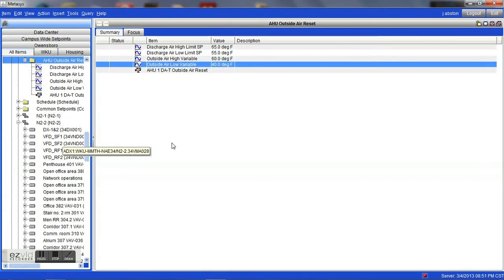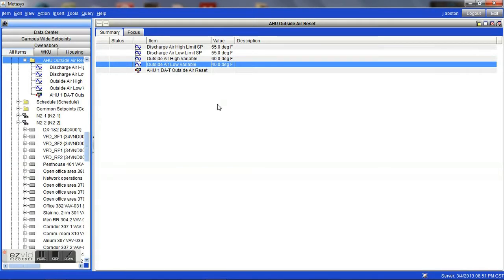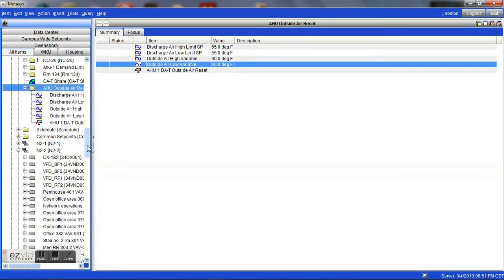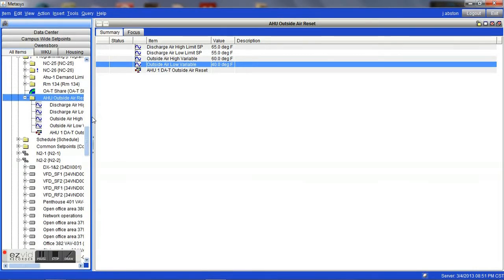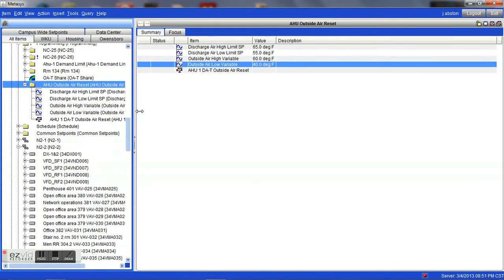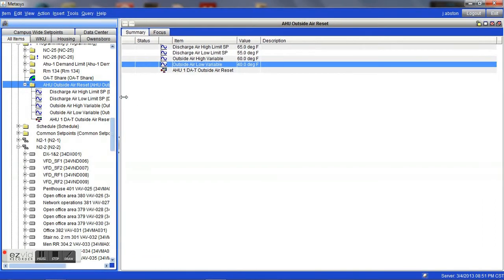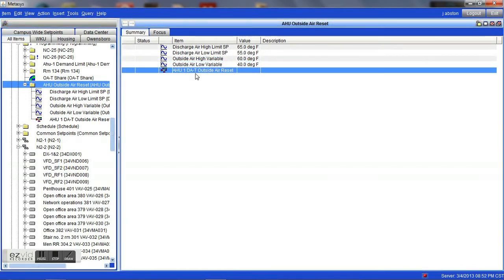One of the first things that we will need to do is to create a few analog value bits. This can be easily done through simply adding them to a folder somewhere where we can find them. Here you can see that I have them in a folder labeled air handler outside air reset. And those elements, of course, the first thing that we will need, which is not in this particular folder, is the outside air temperature. However, it will be pulled into our logic loop.